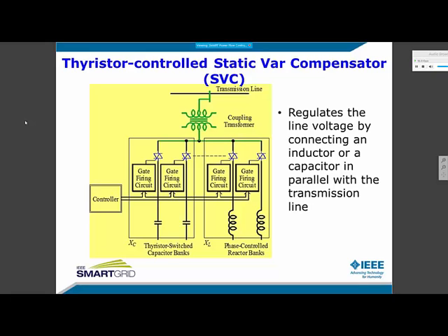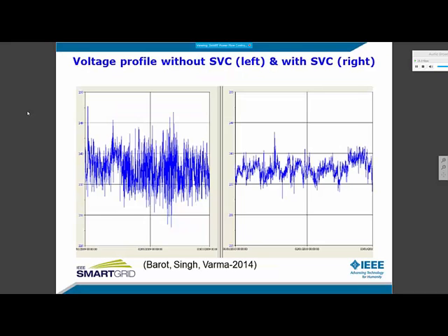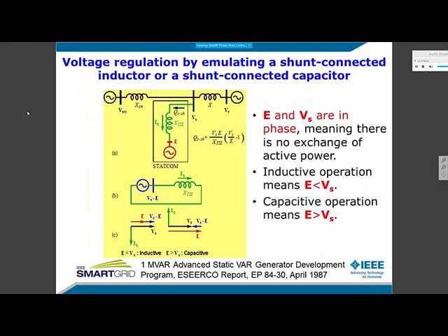The static VAR compensator creates a variable inductor by varying the duty cycle of these back-to-back thyristors. Banks of parallel-connected capacitors and variable inductors together act as an inductor or a capacitor as a whole. This variable inductor and capacitor regulates the line voltage, as I explained in the last slide. The point of compensation of the transmission line is regulated by varying the duty cycle of these switches. This is the power electronics solution. Power electronics thyristor switches make it possible to improve the voltage profile as shown here, and that is good enough for most applications, even though a power electronics inverter can give a superior solution.